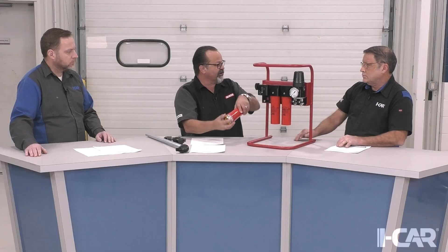So every 6 months, this first stage - you'll see how easy this 500 series is removed, just a little 1/8 of a turn. Inside this canister is a polished aluminum housing with an auto water discharger, or auto drain, on the bottom that's fully automatic. Even under full air pressure, it will still purge when moisture gets inside the float level.